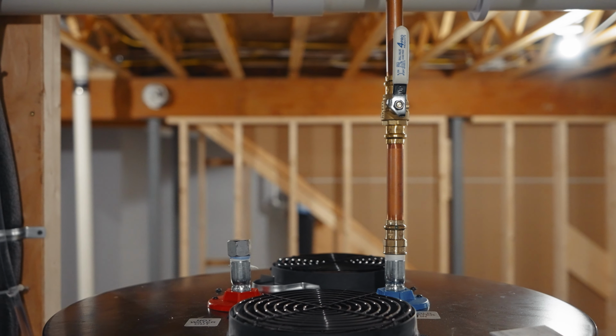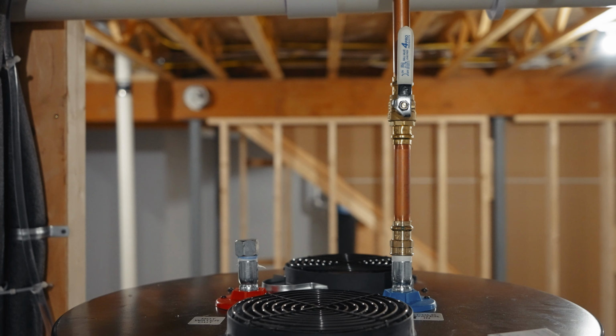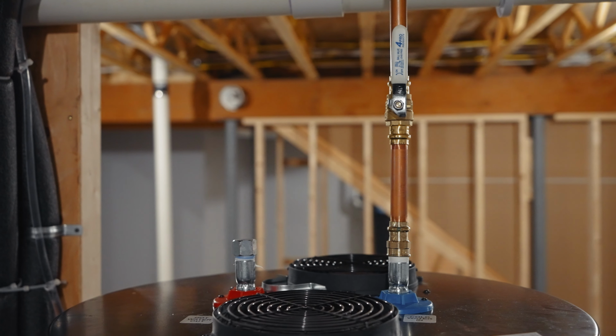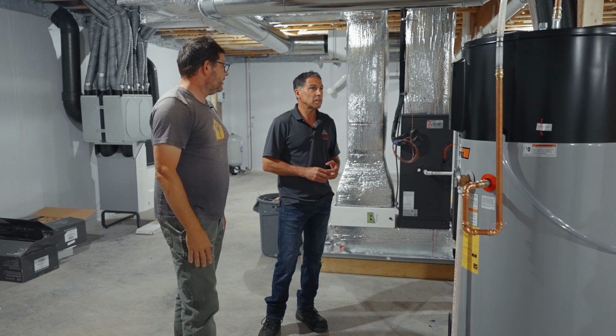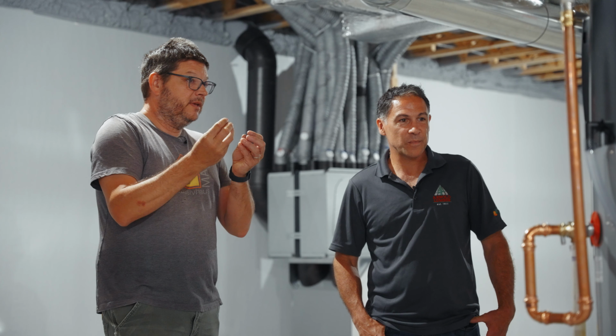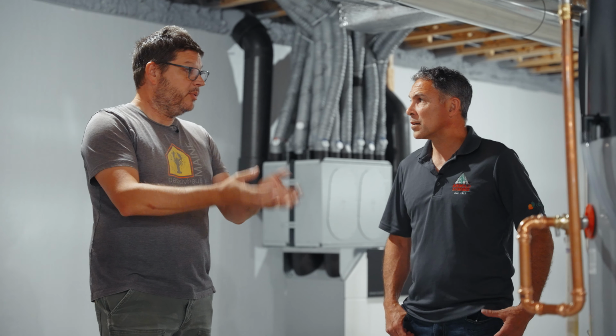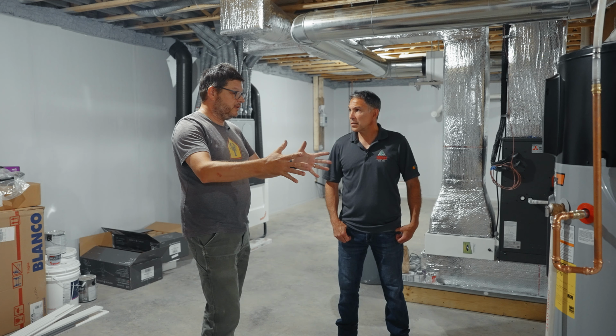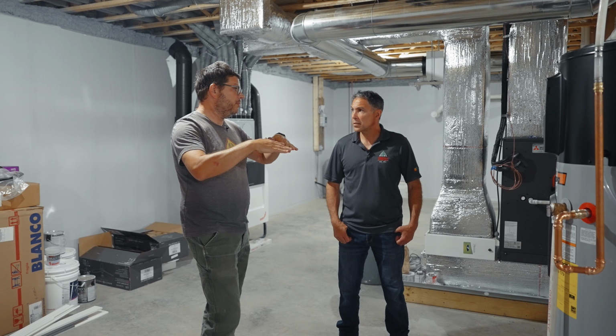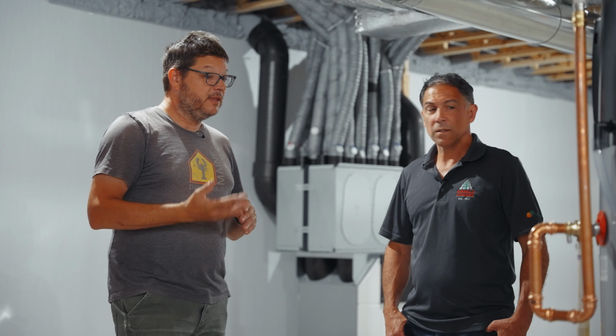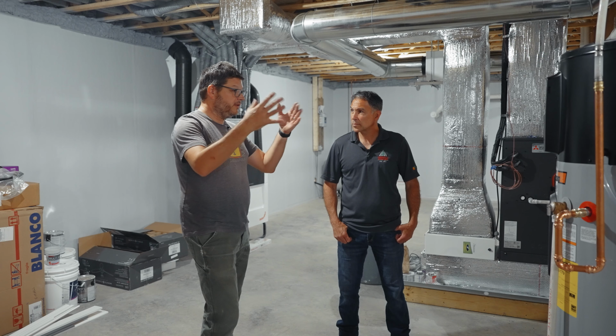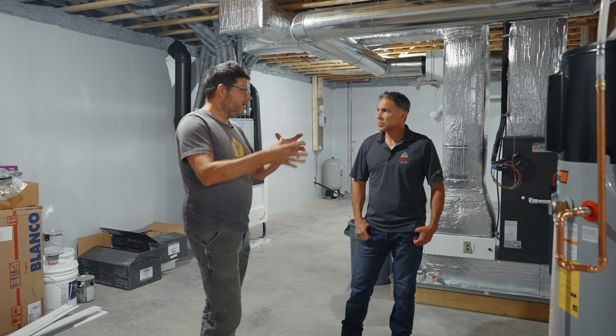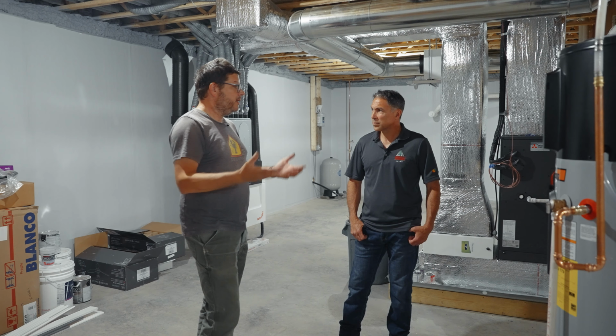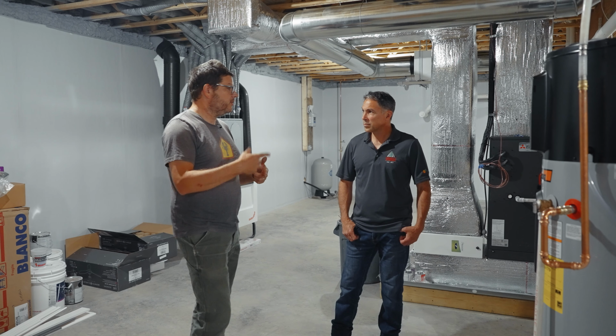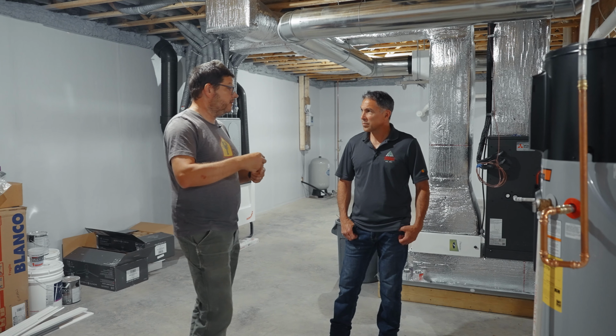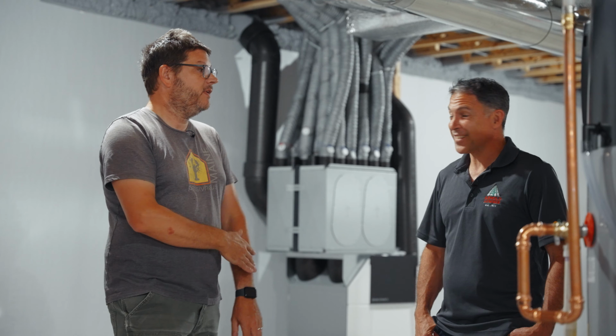This has a filter—there's two grills up here, and there's a filter in the intake air that has to get cleaned every so often. Basically this is pulling a little bit of heat out of the air and putting it into the water, so generally it will lower the temperature of a room 6 to 8 degrees or so. But the other nice benefit is that when it's running through that heat pump cycle creating hot water, a byproduct of that refrigeration cycle is it pulls moisture out of the air—it's dehumidifying. So it naturally dehumidifies the basement as well.